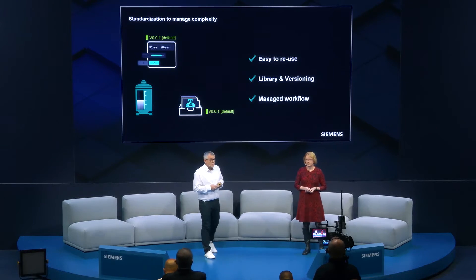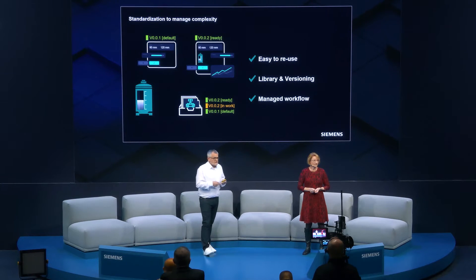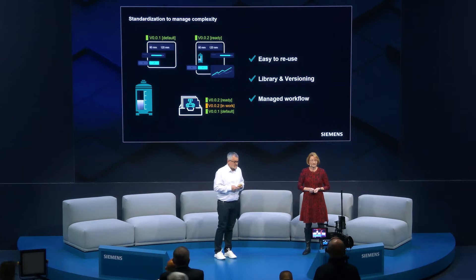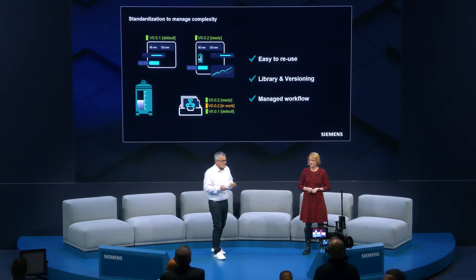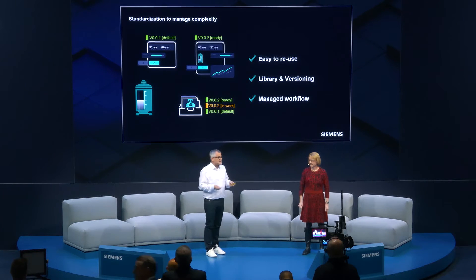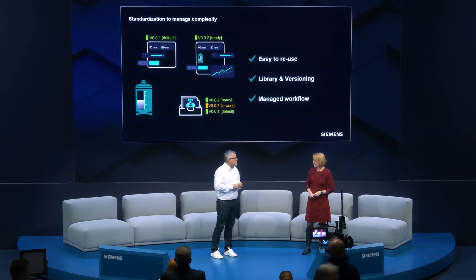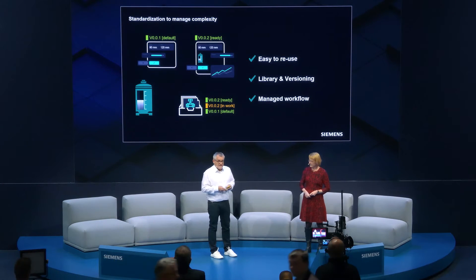Consistency across those platforms is definitely an enormous advantage during engineering. But integrators have to deal with multiple versions and devices — how can they manage this complexity? The best way to manage complexity is standardization, and this is one real strength of WinCC Unified version 18. Starting with the graphical elements — in our words, face plates. Face plates are reusable elements which can be a typical single screen element like a tank or a motor, but also an entire screen to operate that tank, including dynamization. And with version 18, face plates can be nested within face plates.